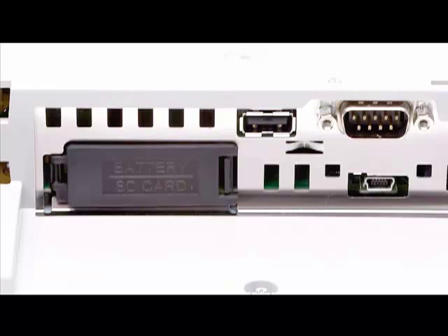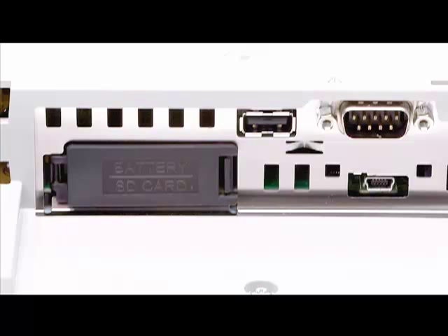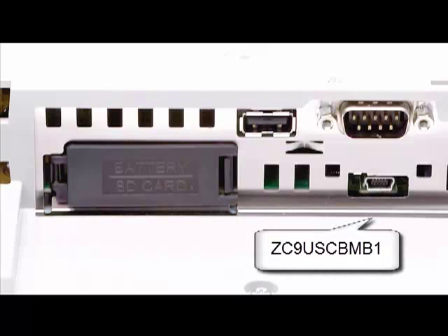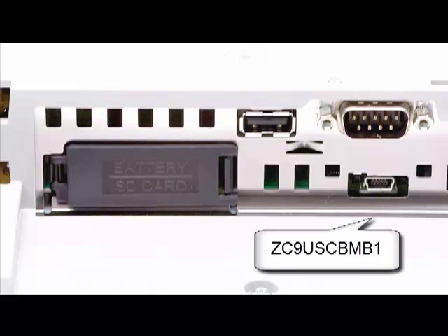Directly below the COM1 port is the USB mini port. This port is used for program transfer to the HMI via a PC and GP Pro EX. ProFace offers the ZC9USCBMB1 cable for this, but a regular high quality USB-A to USB mini-B male cable works.